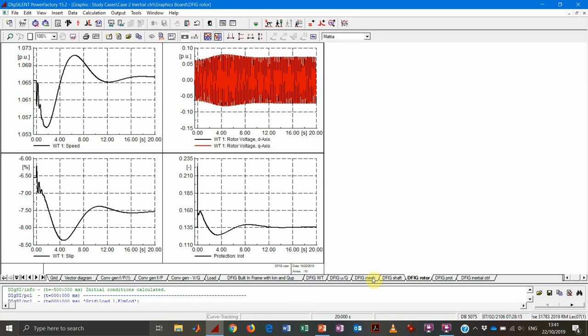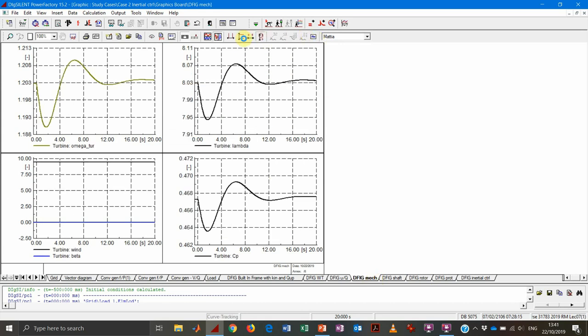Why do we need to reaccelerate the machine? It's not just about speed for its own sake — it's because the rotational speed, given the same wind speed conditions (which most likely won't change in this short time), determines the efficiency operating point of the machine. If we change the rotational speed we move the machine to a different, likely lower, efficiency point and reduce production. So yes, we can give some kinetic energy, but as a steady-state contribution it would be lower. That's why we need to restore the rotational speed to return to the optimal output point.